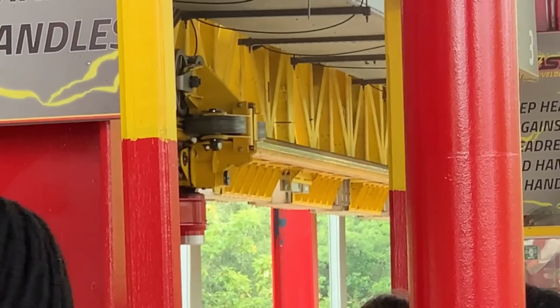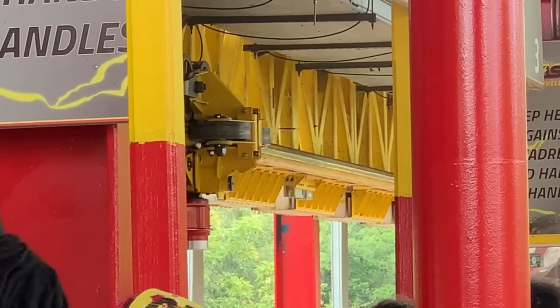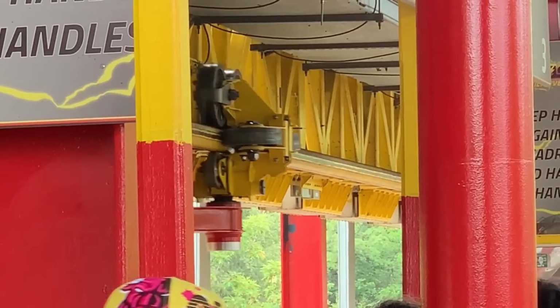Now, a lot of times, troubleshooting like that, you'll need a second person anyway, because a lot of times you'll get it lowered down to one brake that might be having a problem, and you need to see something. Typically, it's always on the other side of where you are, that you can't be at that MOM panel and the brake at the same time. So you need someone else to operate it either from the MOM panel or from the main operator's panel while you're out there doing more troubleshooting at the time. So the MOMs will run stuff like that.